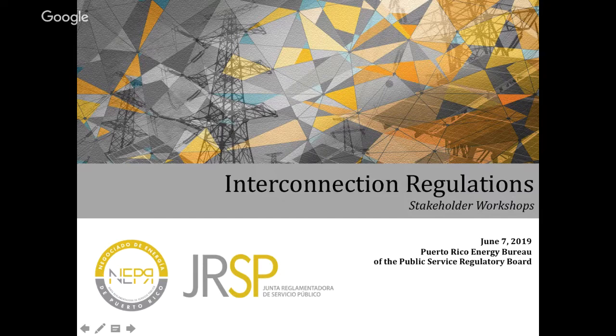Okay, what we have to do is report our recommendations to the commissioners. So would it make sense to consider the graphs or tables on CGIP, which show the distance between the circuit and the substation, along with the voltage level? Would it be feasible? Because if there are tables developers can consult, there's more clarity. It's not a matter of submitting for interconnection just to see what you're told, and maybe being sent to supplementary review that takes three months. From the tables you'd already know the level, and from there you can design and develop the survey that is necessary.